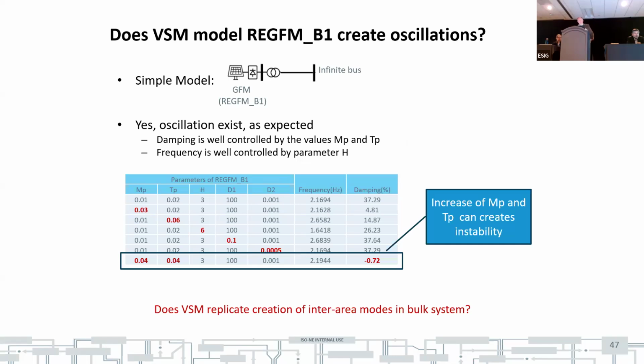And this simple test actually confirms that. So if you change parameters of the inverter, you can easily control damping and frequency of oscillation, and even create instability. But the key question, that is good because the initial intention and the result are consistent.